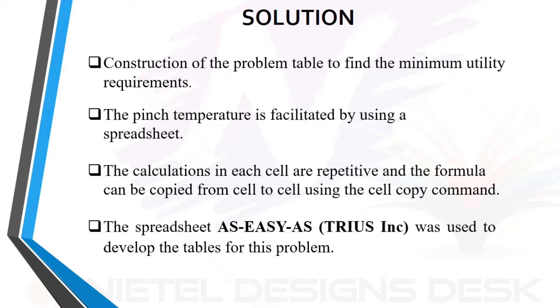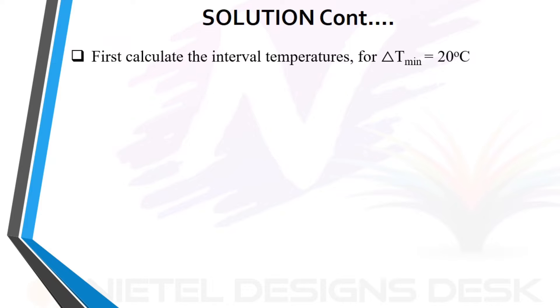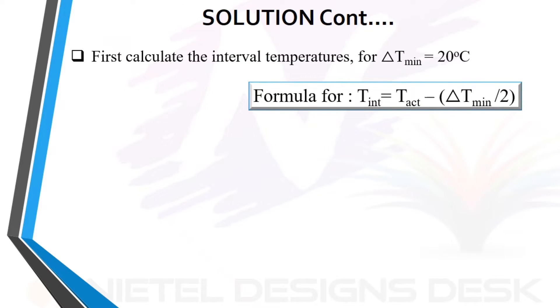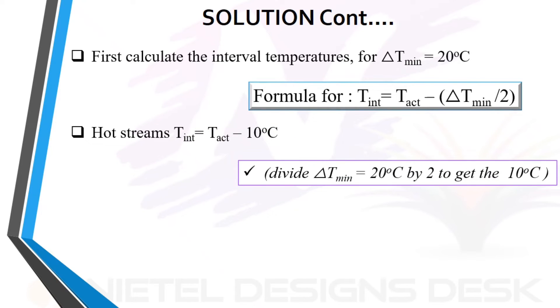A video on how to develop the tables will be posted soon — if interested, drop a comment in the video's comment section. First, calculate the interval temperatures. For hot streams, T_int equals T_act minus ΔT_min divided by 2, and for cold streams, T_int equals T_act plus ΔT_min divided by 2.